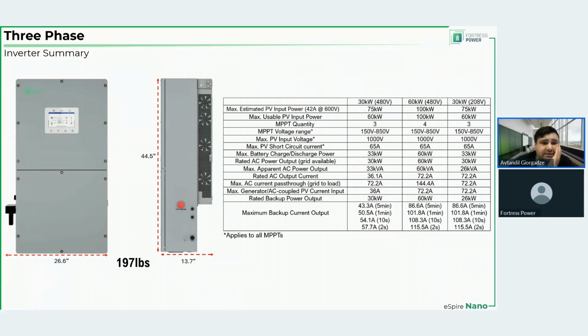Because these inverters are so capable, it's not surprising, I think, that they weigh around 200 pounds each. There are many features, the robust construction, them being outdoor rated and having extra insulation, the cooling circuits and so forth, that result in the inverter being on the heavier side. But for a commercial inverter, nothing there is unexpected to me.